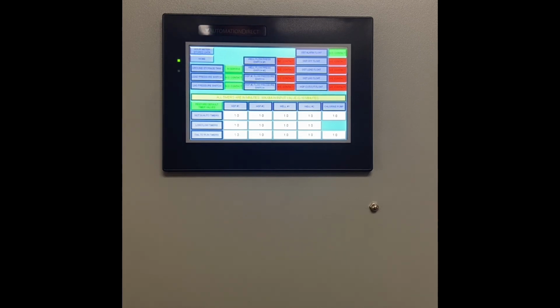Now, the groundwater storage tank up at the top is a little bit different. That is nothing more than changing the control algorithm on how the wells and the high service pumps will behave. If the groundwater storage tank is removed from service to be cleaned, or because there is some other issue or some routine maintenance that needs to be done, then we will touch that and put it in bypass. Note, this button does not move any valves. It does not control any of the piping in the system.